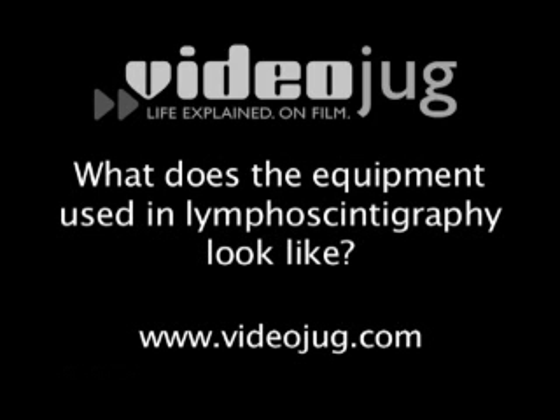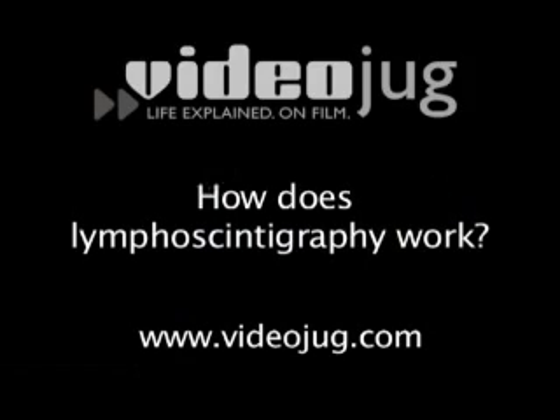What does the equipment used in lymphoscintigraphy look like? Well, the equipment that is used for lymphoscintigraphy is basically the same as the one we use for general nuclear medicine and for cardiac nuclear medicine. There's really no difference. It's basically a gamma camera system that has detectors for detecting gamma rays to form an image.